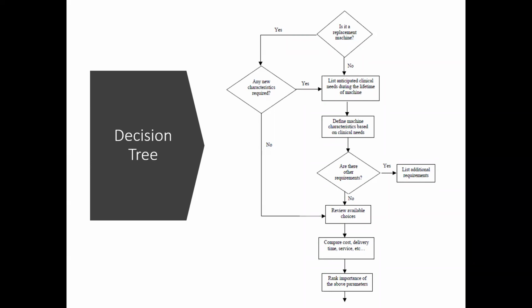Are there any additional equipments that are required? For example, if I'm going to buy a standard LINAC, I may be requiring a standard CT simulator and the treatment planning system. If I'm going to buy an advanced LINAC, certainly the associated equipment, the CT simulator, would require an advancement as well in order to be compatible with the linear accelerator. So this associated equipment is also very important. Definitely the quality assurance equipment should be of that level as well.